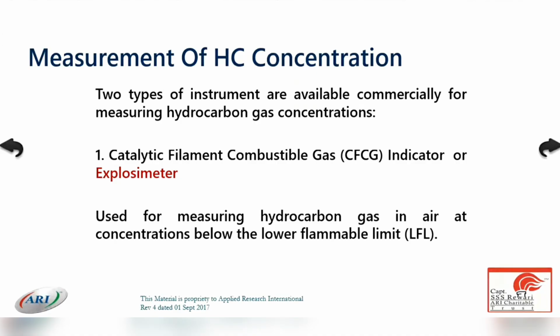The explosive meter is used to measure the gases. We measure the hydrocarbons in LEL form. Now, what is the lower explosive limit? When the hydrocarbon percentage is measured and it is less than LEL, explosive meters are used. The oxygen percentage has to be more than 11% for an explosive meter.